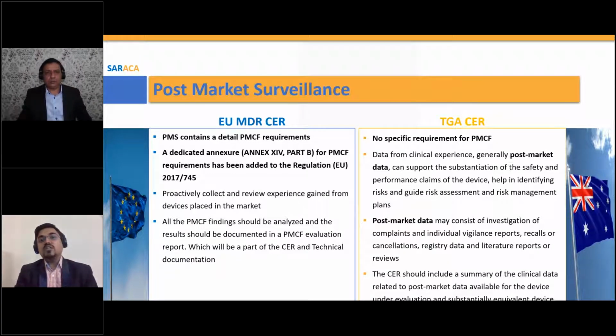You can have only your post-market data. The post-market data only contains your vigilance data, your investigations, your recalls, any FSCAs, field safety corrective actions, or cancellations, or any registry data. You can just review the registries, government registries, or your own company's registries, or you can do a literature survey to find out the complaints.